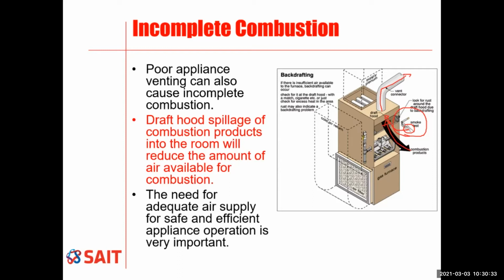Okay, so you could do a quick check to see if this appliance is back drafting. And this is a dangerous situation. If this appliance were to fire, all the products of combustion would be pushed into the building or the room that this is housed in. And that would be a problem.